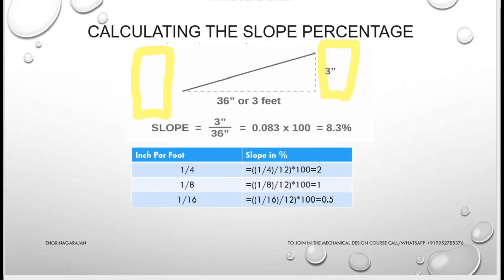Let me quickly explain what 1/4, 1/8, and 1/16 inch per foot means as a percentage. Assume a pipe falls 3 inches over a run of 36 inches (3 feet) between two manholes. The slope is 3 divided by 36 = 0.083, multiplied by 100 = 8.3%. In our case, 1/4 inch per foot means (0.25/12) × 100 = 2% slope. Similarly, 1/8 inch per foot gives 1% and 1/16 inch per foot gives 0.5% slope.